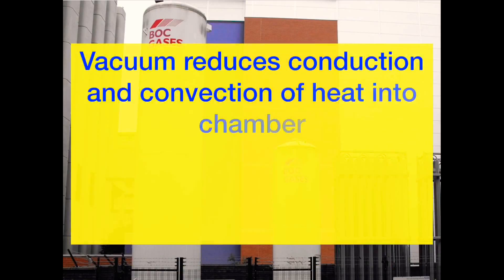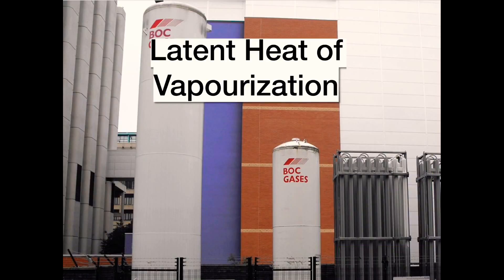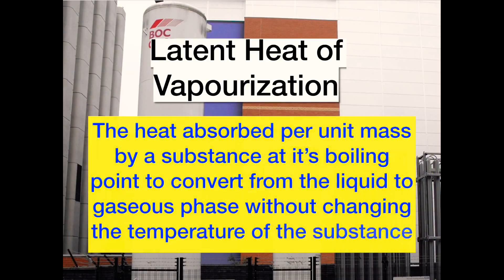The VIE relies on minimisation of conduction and convection of heat into the chamber, causing only a small amount of heat to enter. This heat causes vaporisation of liquid oxygen, which, via the principle of latent heat of vaporisation, causes a cooling effect on the remaining contents of the VIE.